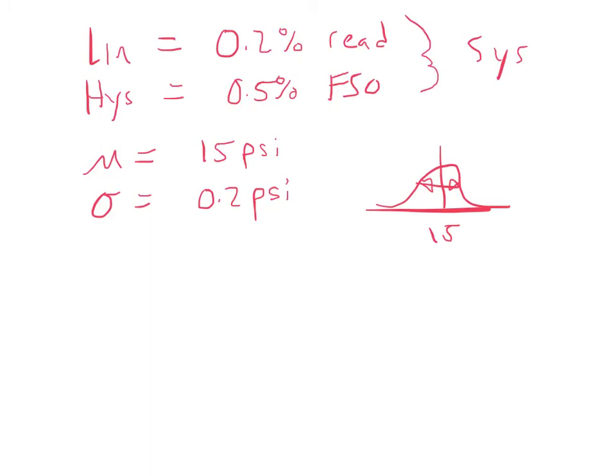How you deal with the hysteresis error? Well, it says it's 0.5% of the full-scale output. But we need to know our full-scale output of this sensor. And so, we'd have to look at the manufacturer's specifications. And we can maybe say, let's say our pressure reading can measure anywhere between minus 30 to positive 30 psi. So, there's our full-scale output.